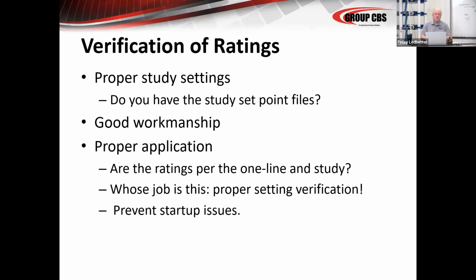Do you have the study set point files? All these instruments, all these relays, all these protected devices, all these breakers are supposed to be a particular frame rating, a particular current rating, a particular voltage class, and a particular IC rating. Now, we're going to get into breakers, particularly in one of the next sessions, and I'll explain all that to you. But a circuit breaker is basically the sentinel that's standing vigilant guard over your system. And it has a voltage class, it has a frame size, it has a continuous current rating, and it has an IC rating. So the IC is the bursting pressure, essentially.